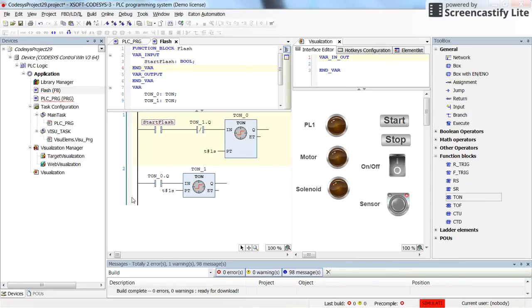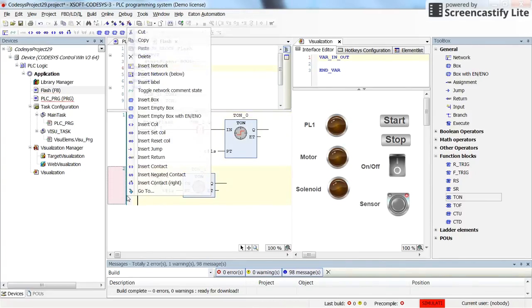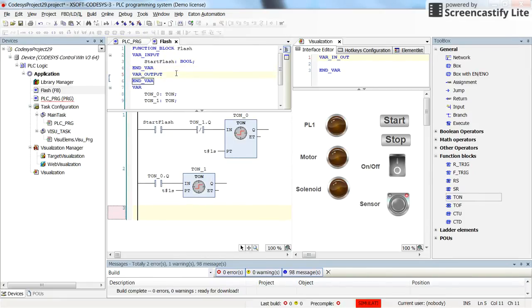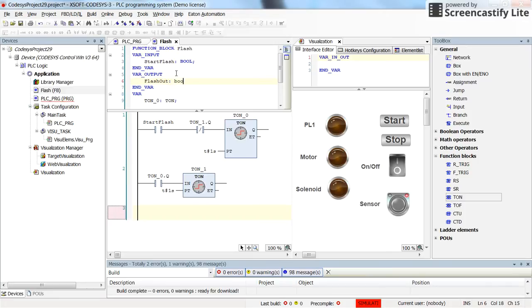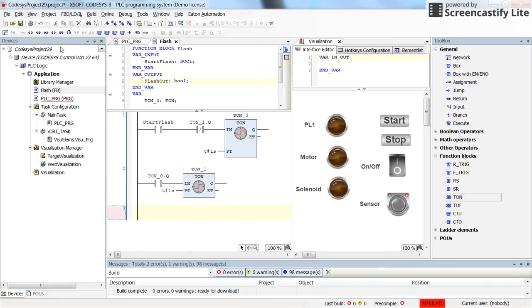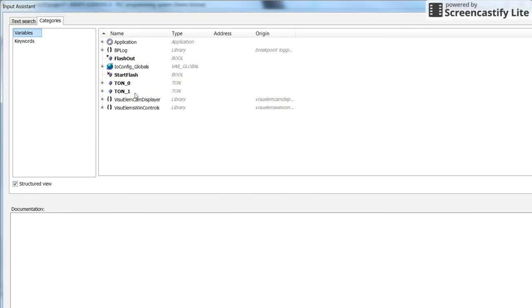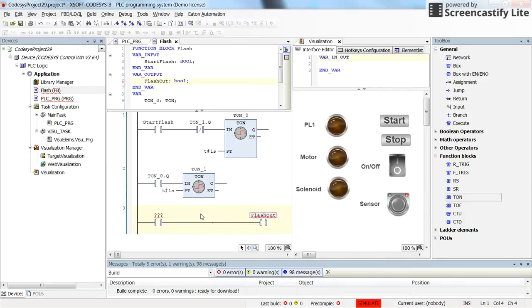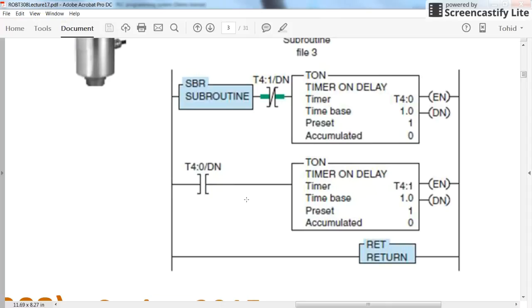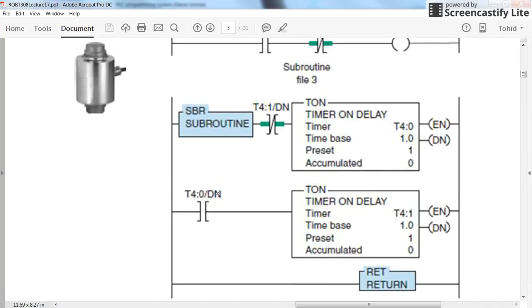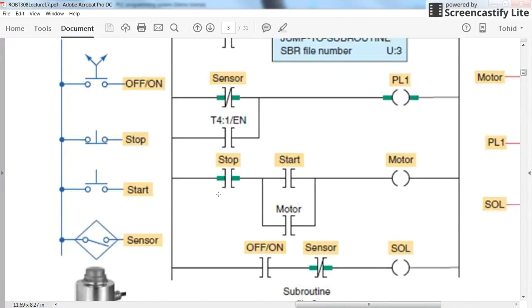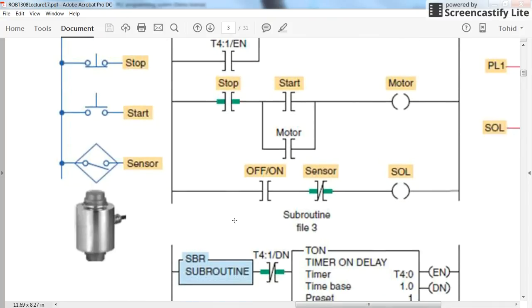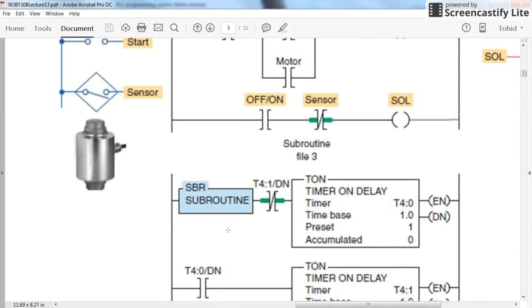As an output I am going to create an output variable. So I will call it flashout which is of type boolean. And assign the value for this output variable. So this is flashout. And it will receive the data from the either enable bit of second timer or done bit of the first timer. Because if you look here, this is what we get from the subroutine. The enable bit of timer one or the done bit of timer zero.